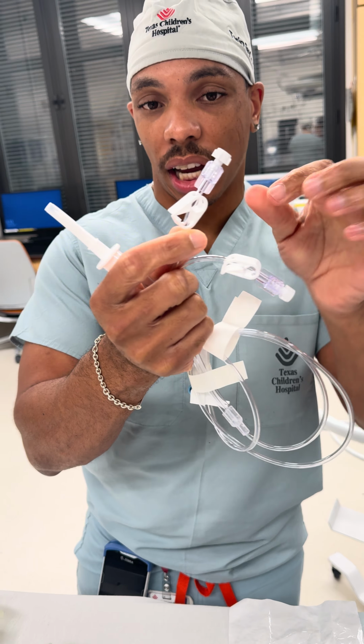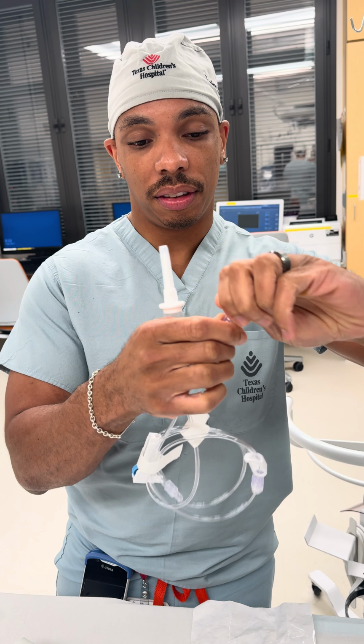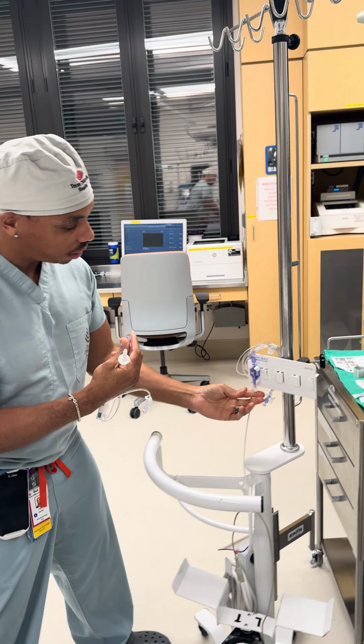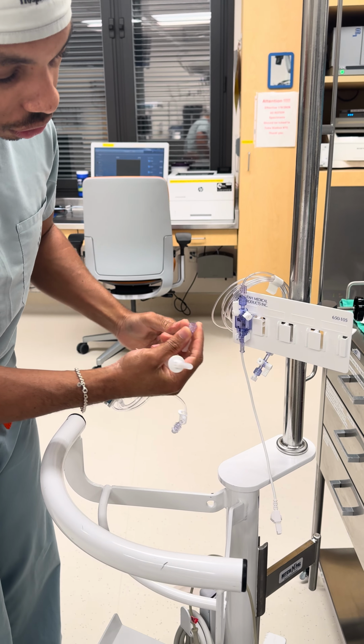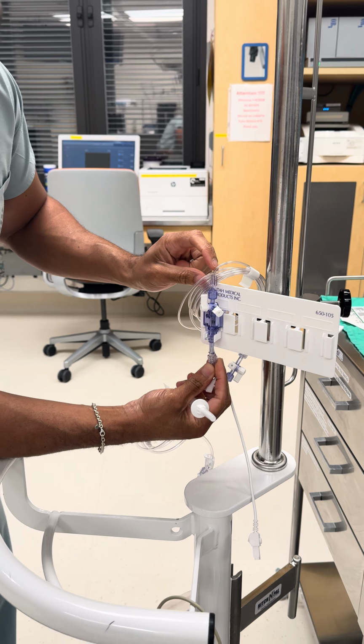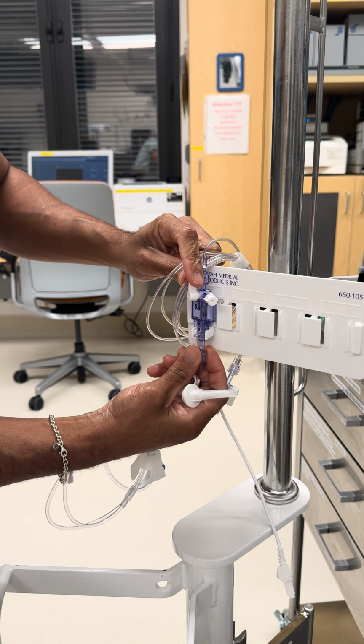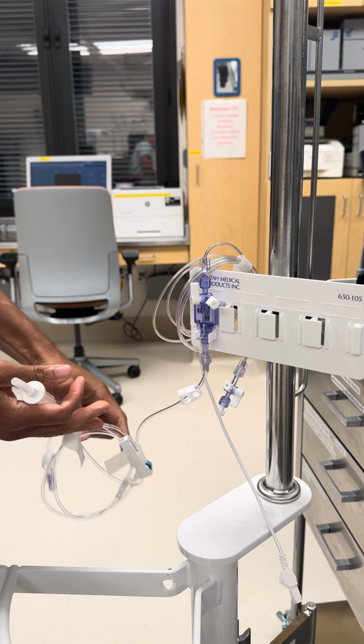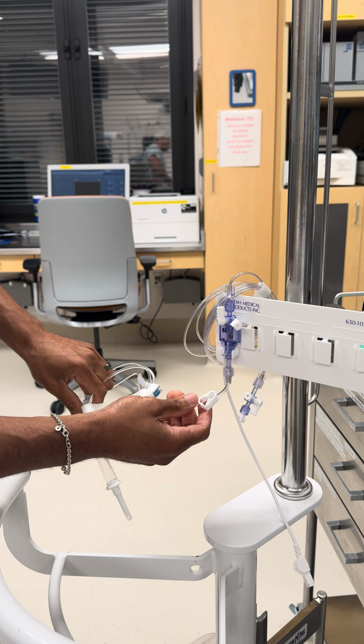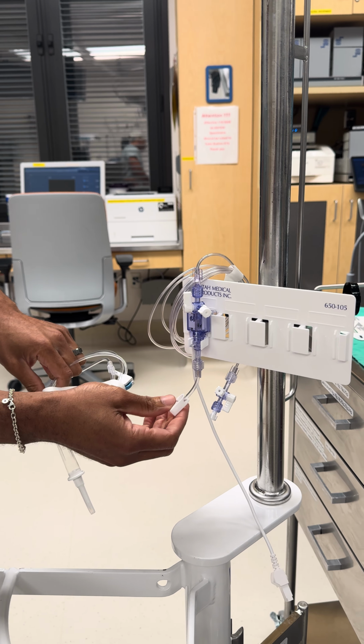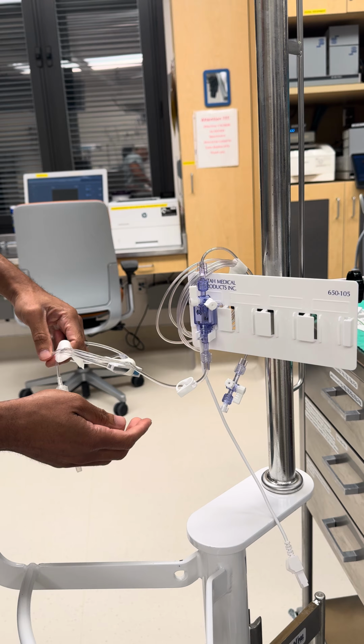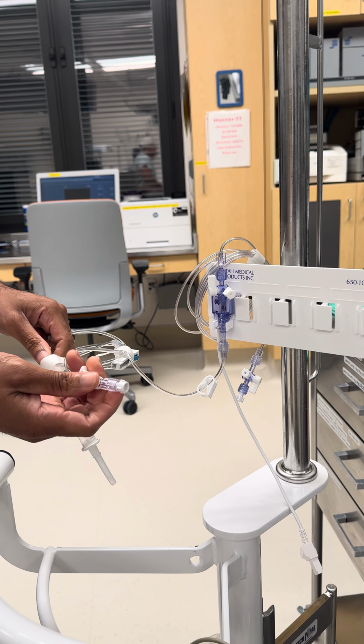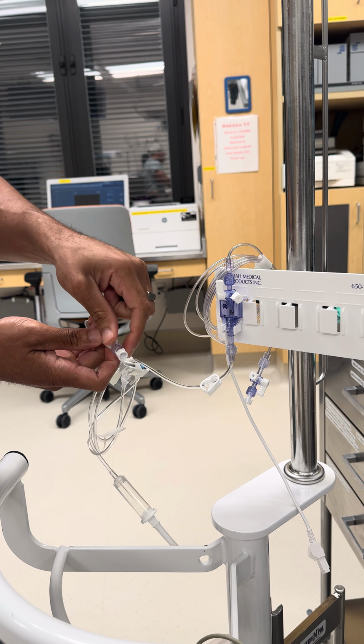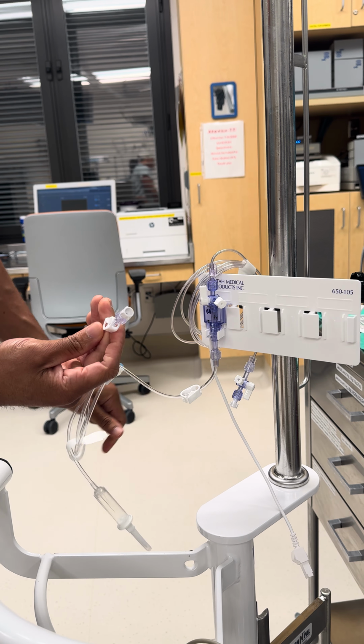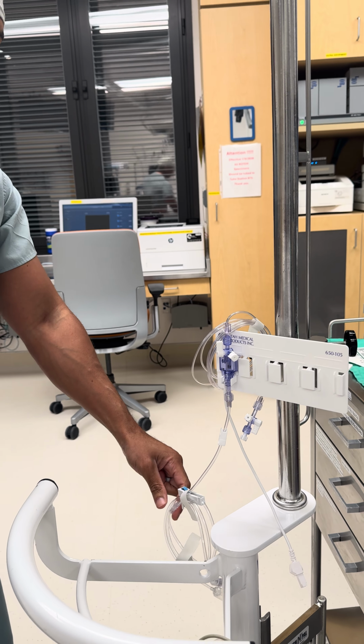Now, with the open side, you're going to take it, go to the bottom of the transducer, twist, and connect. So we're good to go there. And the reason why we're going to leave this one open is because this is the side that the pressure bag is going to go, the normal saline is gonna go through. This side we want clamped, because if you don't clamp it, the fluid's gonna flow out. So we wanna make sure that this one's unclamped and this one's clamped. So we can set it and forget it.